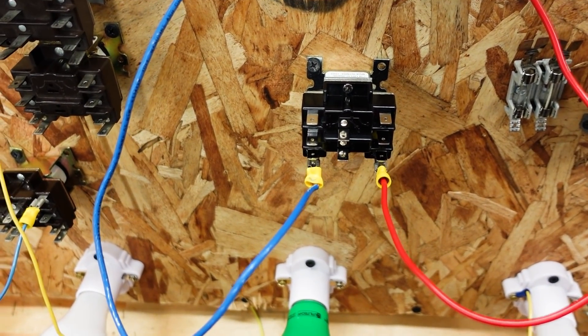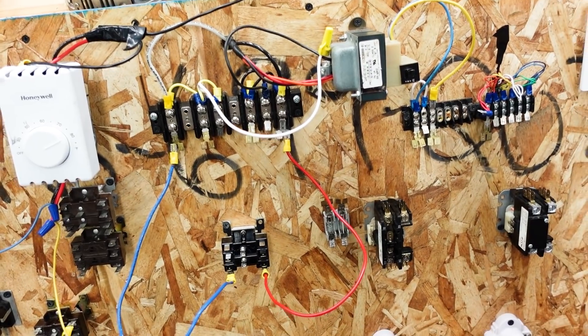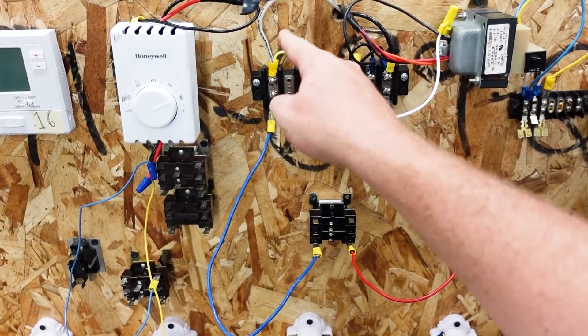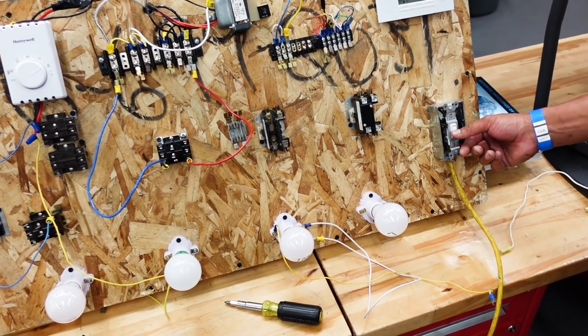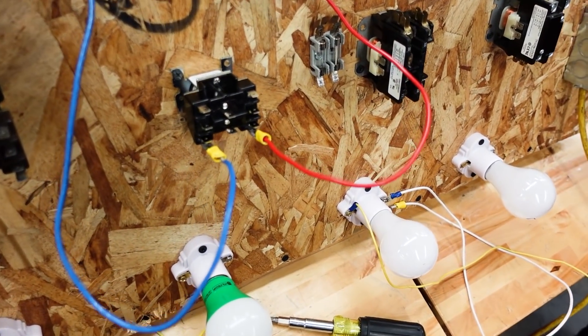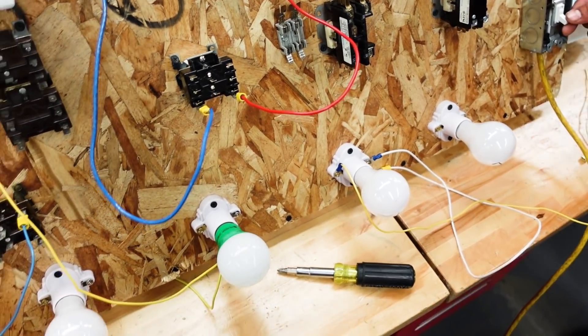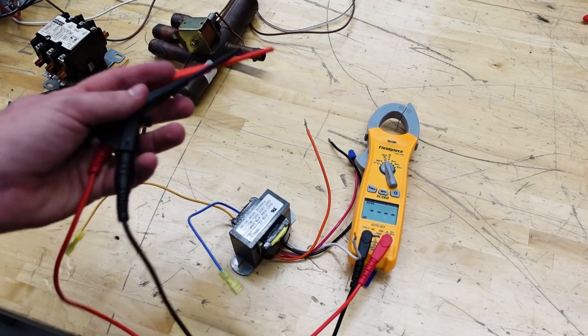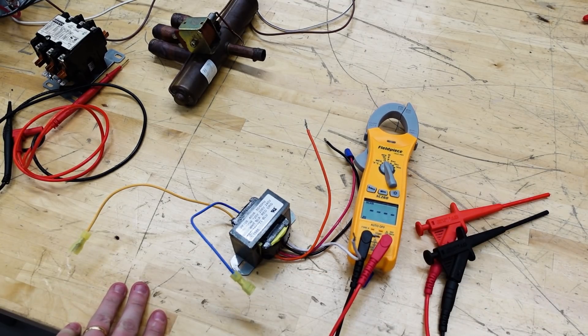Chad wired up relay to 120 volts. If we back up here, you can kind of see it's coming directly from our incoming power. 120 volts to the coil, flip the switch. It's amazing how a 120 volt coil relay works best when you put 120 volts to it. So there you have it. A lot of different ways you can use an ohmmeter and also pay attention to your data tags. Thanks for watching.